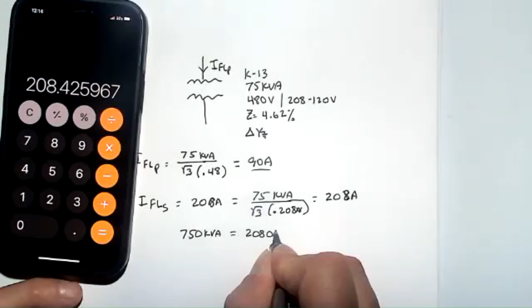And again, that's just a side note. Again, rule of thumb, something to think about, something to remember in the back of your mind. And as I said in the previous page, what if it was 300 kVA? Well, if it was 300 kVA, it's 4 times this number. So an easy calculation for you to remember. Now, so that's full load amps, primary and secondary.